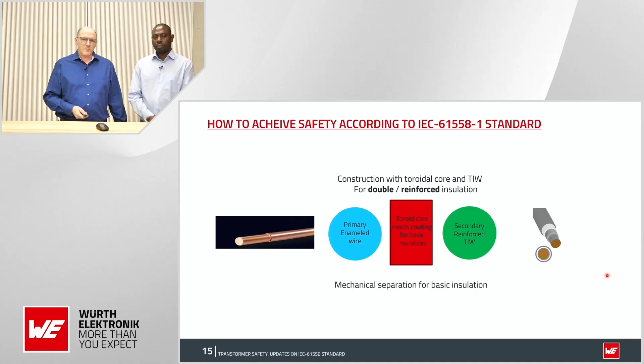And this is not because of safety between the core and the windings. It is more a mechanical separation to save the wire, so that the wire is not damaged when we wound it directly on the toroid. You can see primary side again an enameled wire, and secondary side, in this case, a triple insulated wire, the same picture as Antwi showed before, with the copper in the middle and 3 layers of isolation on top. So the next design I want to show is primary side with the basic insulated, fully insulated wire, and secondary side with the reinforced fully insulated wire.